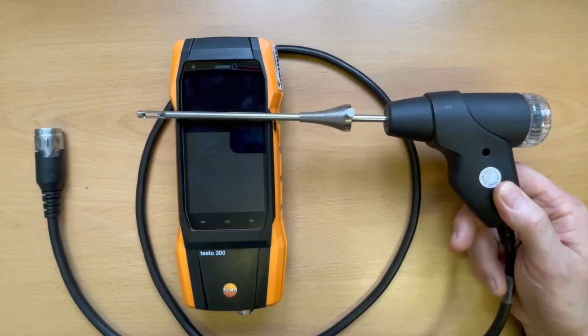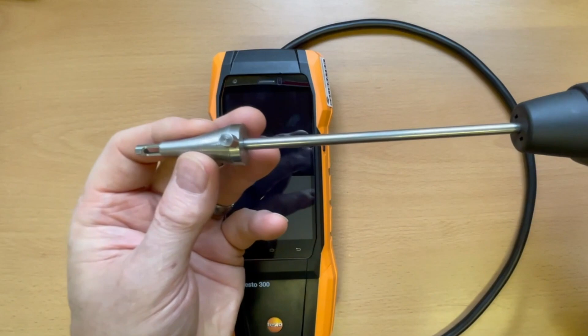So before we move on to turning the machine on, let's have a look at the probe. We've seen the plug at the end and how that works, so let's look at the probe itself. As usual, the probe has a stop or seal for when you put it into the analyzer port, but this one comes all the way off, and I don't really like that idea because you end up losing them. Some manufacturers make the end bigger here so it doesn't fall off, but TESTO haven't.